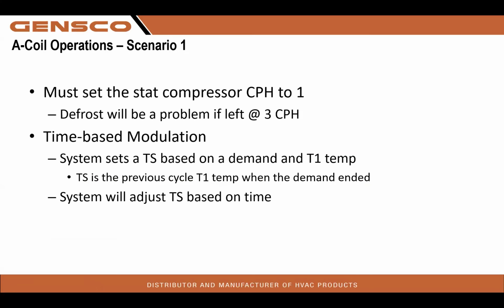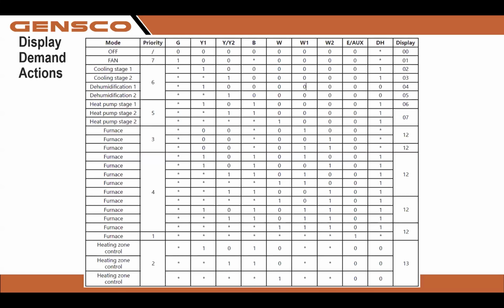When we are running an aftermarket stat, T6, 8000, what have you, we must set the compressor cycles to 1 per hour. Defrost will be a problem if left at 3 cycles per hour or more. We do go on a time-based modulation. System sets a TS based on a demand and T1 temp. System will adjust TS based on time. More scenarios in the display on your indoor board.